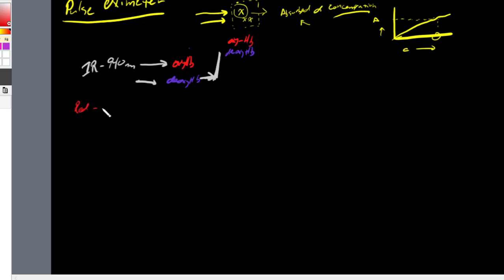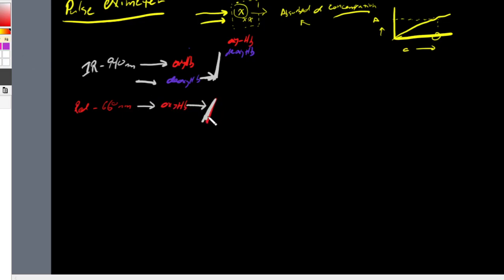Red light at a wavelength of 660 nanometers does not absorb oxyhemoglobin — you'll see red light being transmitted through oxyhemoglobin. But with deoxyhemoglobin, if you shoot red light through it, you will not see that light transmitted to the other end. So deoxyhemoglobin absorbs red light.